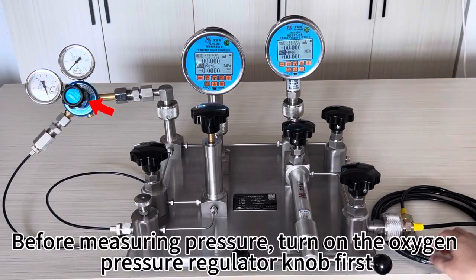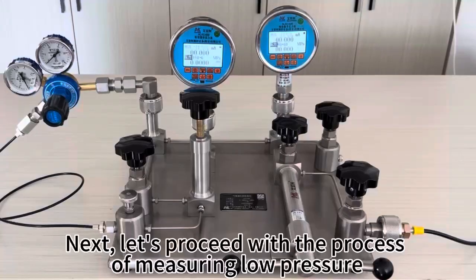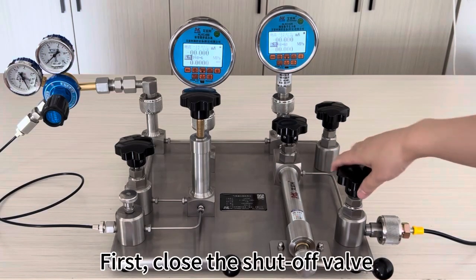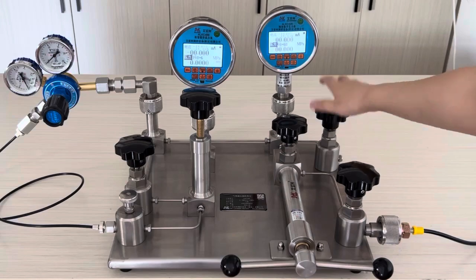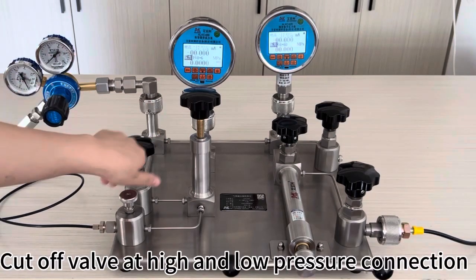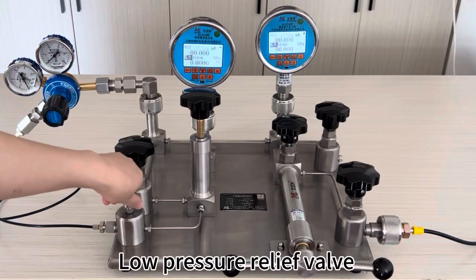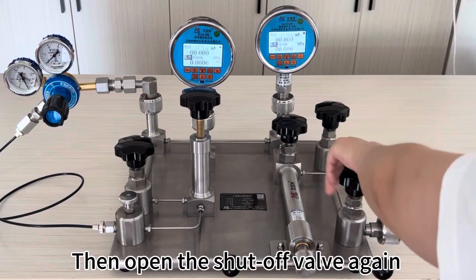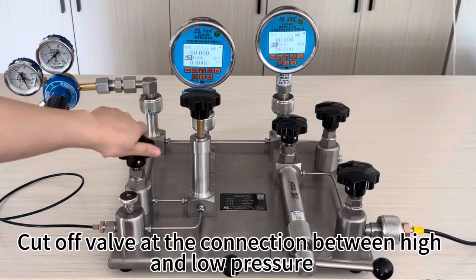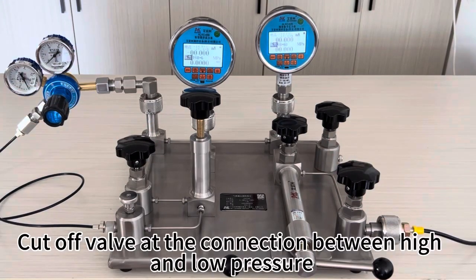Before measuring pressure, turn on the oxygen pressure regulator knob first. Next, let's proceed with the process of measuring low pressure. First, close the shut-off valve, high-pressure relief valve, cut-off valve at high and low pressure connection, low-pressure relief valve. Then open the shut-off valve again, cut-off valve at the connection between high and low pressure.